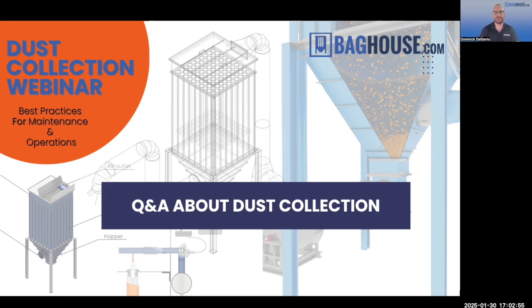Mind sharing that? Yeah, sometimes people think that the hopper is supposed to be full or that there's supposed to be material always within the hopper. The hopper is obviously designed to be able to collect the dust. It does fulfill that purpose, but only on a very temporary timeline, only until it can be released through the airlock. Some places that we go to, you open up the dirty side, and where the hopper is, it just spills dust. That's a huge hazard if it's anything that could start on fire, obviously.